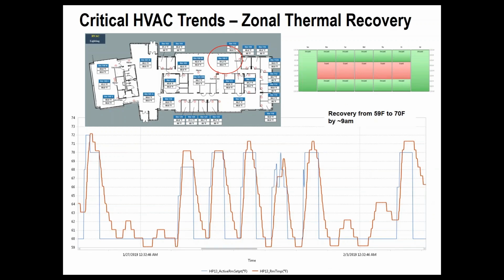Zone thermal recovery. So the worst thing that can happen is to come in on a Monday morning, your space is cold, you're pretty much cold all day, and the space doesn't even recover until that Tuesday. But at the same time, it's important that we don't just throw that out the window and go to a 24/7 schedule. So I wanted to make sure that our morning warm-up scenario was working decently well here, and I did a little bit of an analysis on a very cold winter day.